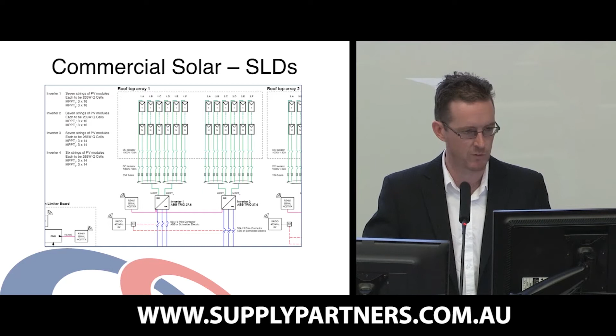Up with the inverters, you can see we're actually using radio networking equipment here. This is an example where the feed-in limiter board is adjacent to the MSB, but the inverter locations are somewhere else. At times you can run physical cable hardwired, and that's great if it works, but other times that can be very difficult or impossible, so it's possible to use radio networking equipment, which we can provide.